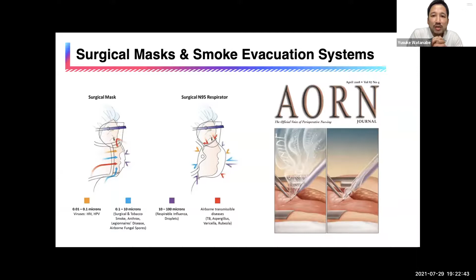A number of smoke evacuators exist in the market. The device contains 3 main features: capture devices, vacuum system, and filtration. Place capture devices ideally within 5 centimeters, and evacuate the smoke as close to the site where it is generated as possible.